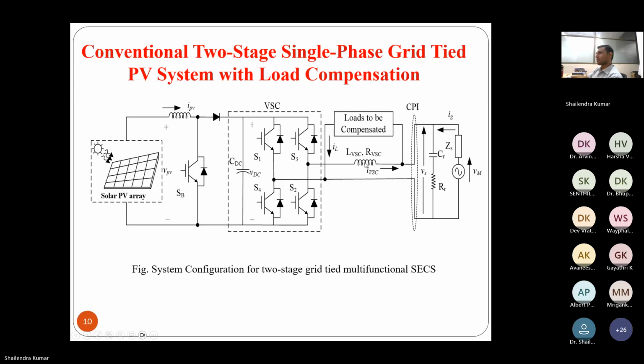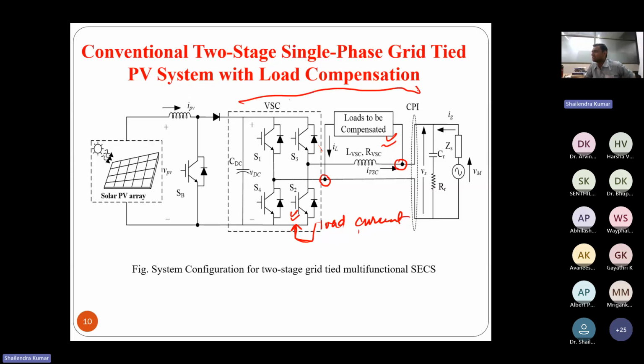What can we do? We have connected one load which has to be compensated here. After this compensation, we have not invested anything in the hardware, only some load feed-forward sensors we have put in the control. So an extra load current sensor we have put here, and through the load current, we are providing the reference to this inverter. So during daytime, it is feeding the power to the grid. So this unit is acting as a DC to AC converter. However, at nighttime, it is acting as a compensating device.